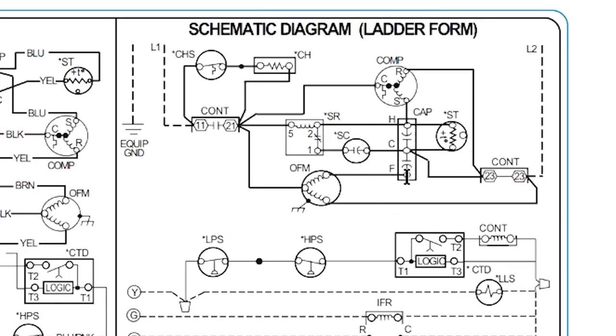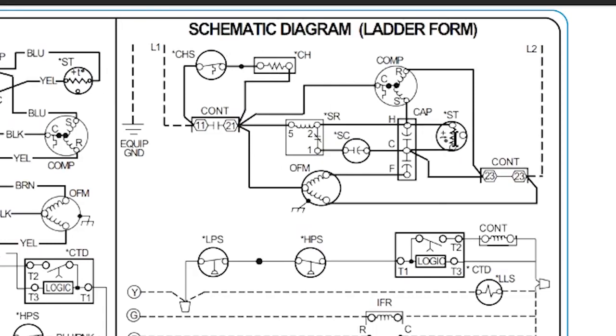The capacitor symbol is a straight line and then a curved line on the other side — straight line and curved line. Whenever you see that, you're looking at a capacitor. A winding symbol with curves means an inductive or magnetic winding. When you see jagged peaks — like on the crankcase heater or the start thermistor — that means the component produces heat. Motors are magnetic so they have the curved coil symbol; the start relay coil is also magnetic.